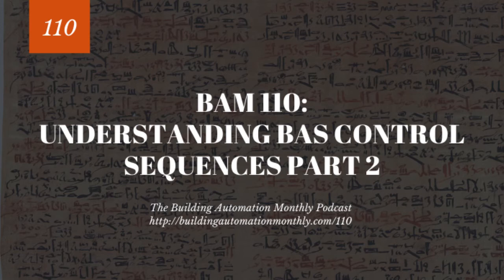Man, we're going down so many rat holes today. But can you see why it's not as simple as just saying, all right, you control the temperature, you control the CFM, you open the damper, you open the valve, you're done. There are so many intricacies, and that's what I find so exciting about building automation, there are so many interrelated concepts. Oh, well, if I close my VAV dampers down and I don't have proper ramp time set on my supply fan VSD, well, then my VSD is going to trip. So I need to be careful there.